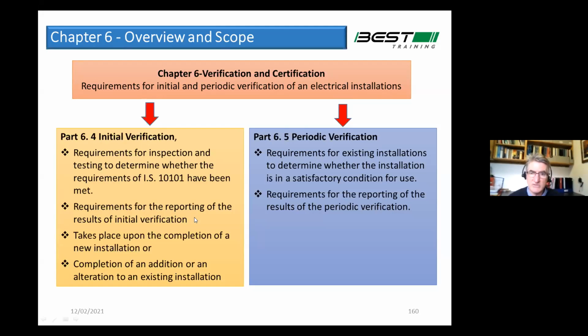Insulation resistance has to be done before you verify. So you put a test initially at 250 volt and then 500 volt, and make sure there is no breakdown in insulation. For example, a cable could have got damaged during the installation. And then post connection, you've got to check things like the operation of RCDs to make sure they function correctly, and most importantly, of course, check your earth loop impedance to ensure that the impedance is low enough to achieve the disconnection times specified in chapter 4, which deals with protection against electric shock.